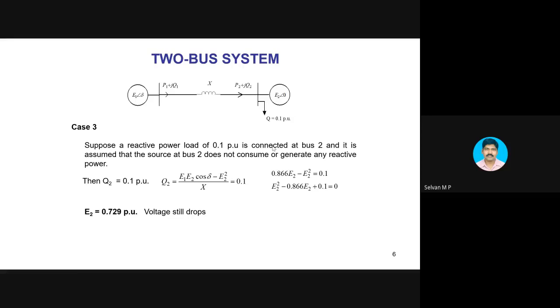That is because of more and more reactive power demand in the system, there are fewer sources to supply reactive power. Even if I have a sufficient source, I should not have it at only one end, I should have it at both the ends in a transmission line. Then only I will be able to maintain the voltage profile. Otherwise, there will be poor voltage and an incident will happen, right? So reactive power is very important at both the ends.